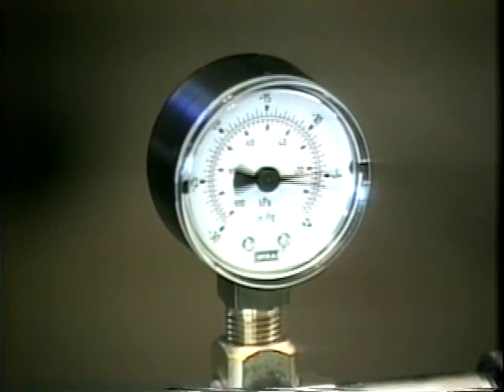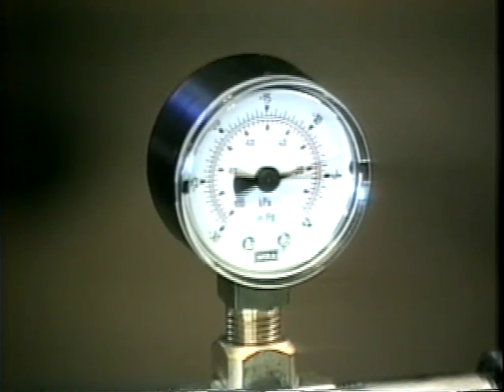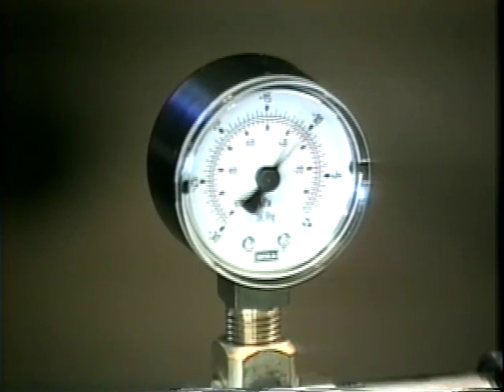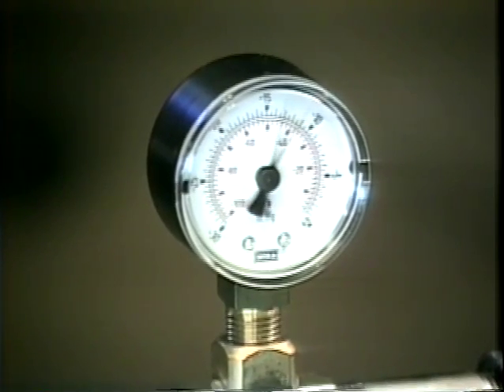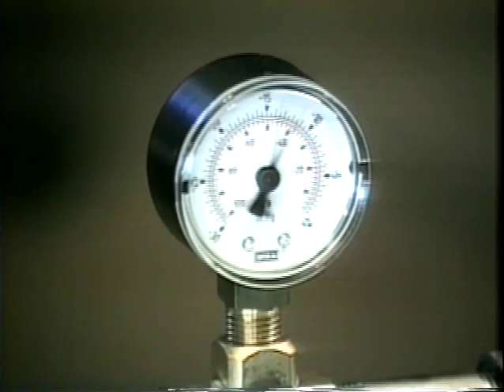When the last slide is placed on the vacuum chuck, it closes the vacuum system. Then this gauge will show an increase in vacuum level. This instrument is very handy to monitor vacuum levels and to indicate if there are any leaks present, such as broken slides.